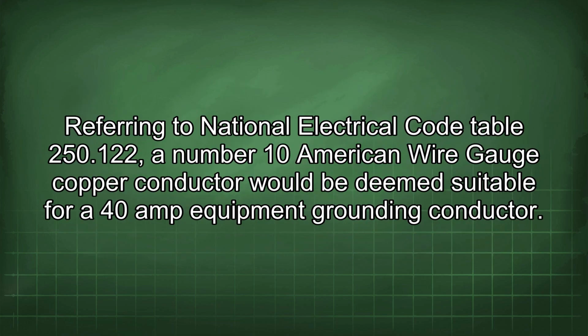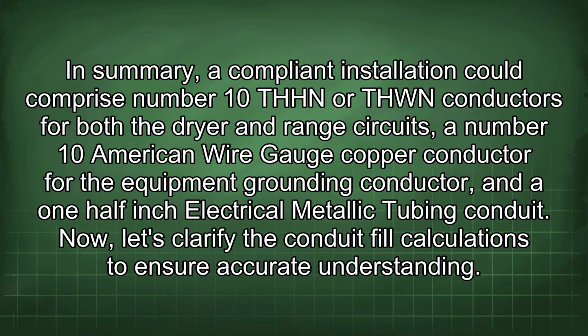Referring to National Electrical Code Table 250.122, a number 10 American wire gauge copper conductor would be deemed suitable for a 40 amp equipment grounding conductor. In summary, a compliant installation could comprise number 10 THHN or THWN conductors for both the dryer and range circuits, a number 10 American wire gauge copper conductor for the equipment grounding conductor, and a 1/2 inch electrical metallic tubing conduit. Now let's clarify the conduit fill calculations to ensure accurate understanding.